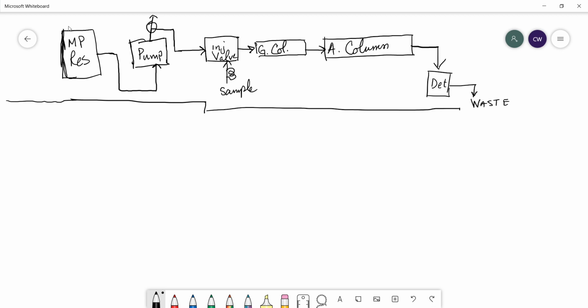Okay, and then the helium pressure helps push your solvent, your mobile phase, into the pump. That way, priming it is very easy. You just turn the pump on full blast and put the outlet to waste. Okay? And that will allow it to suck in enough mobile phase that all the gas bubbles in the pump heads get eliminated. All right. Other manufacturers don't do this. They don't have the mobile phase under pressure. It's not technically necessary. You can prime a pump by simply drawing enough material through it.